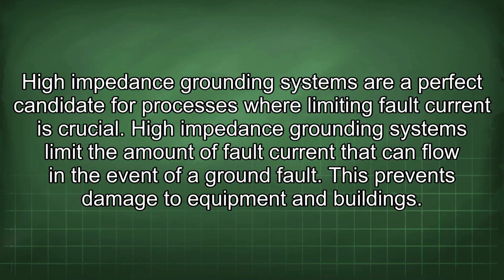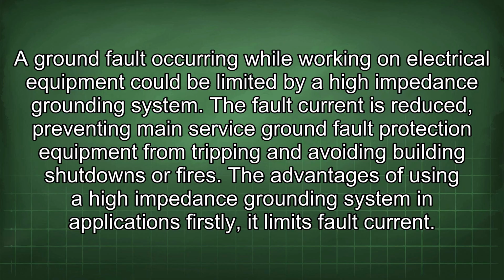High-impedance grounding systems are a perfect candidate for processes where limiting fault current is crucial. High-impedance grounding systems limit the amount of fault current that can flow in the event of a ground fault. This prevents damage to equipment and buildings. A ground fault occurring while working on electrical equipment could be limited by a high-impedance grounding system. The fault current is reduced, preventing main service ground fault protection equipment from tripping and avoiding building shutdowns or fires.